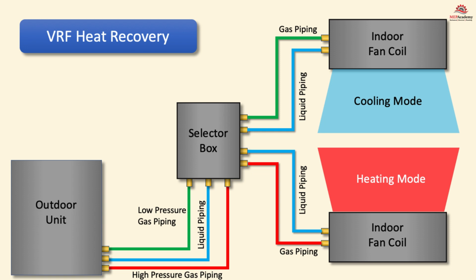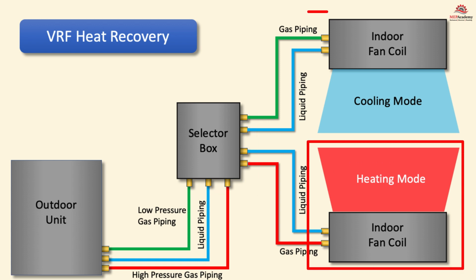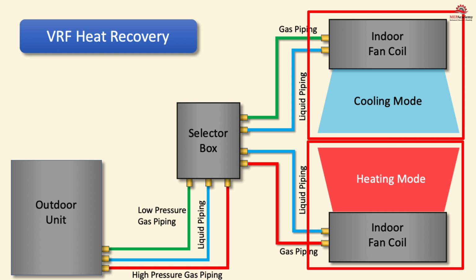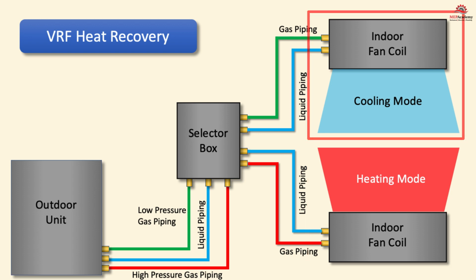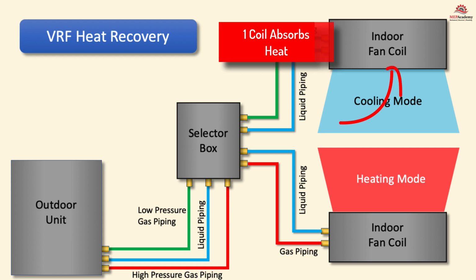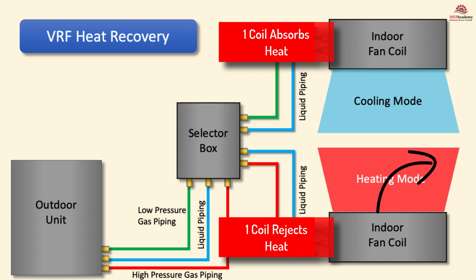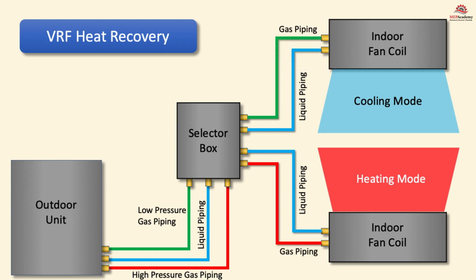With a VRF heat recovery system, the branch controller will either send the heat absorbing or heat rejecting refrigerant to any space depending on whether the space wants heating or cooling, based on the demand of the controller. So, if heat is absorbed into the refrigerant from a space needing cooling, it can be rejected by the refrigerant into a space needing heating. This is the basic principle of a VRF heat recovery system. We'll cover these systems in more depth in other videos.